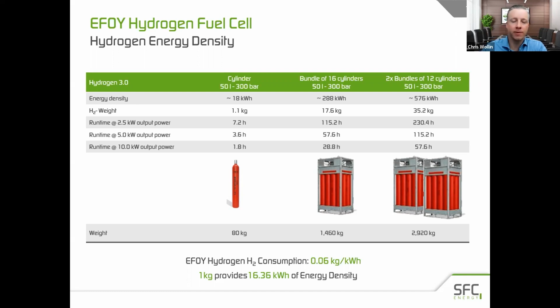If you look at a standard 16-cylinder bulk pack, this provides enough energy density to run a 10 kilowatt load for just over 24 hours, and these can be paralleled together to achieve your desired level of autonomy. So in an emergency backup power scenario, you could parallel 3 of these together to provide more than 72 hours of backup power for your 10 kilowatt load.